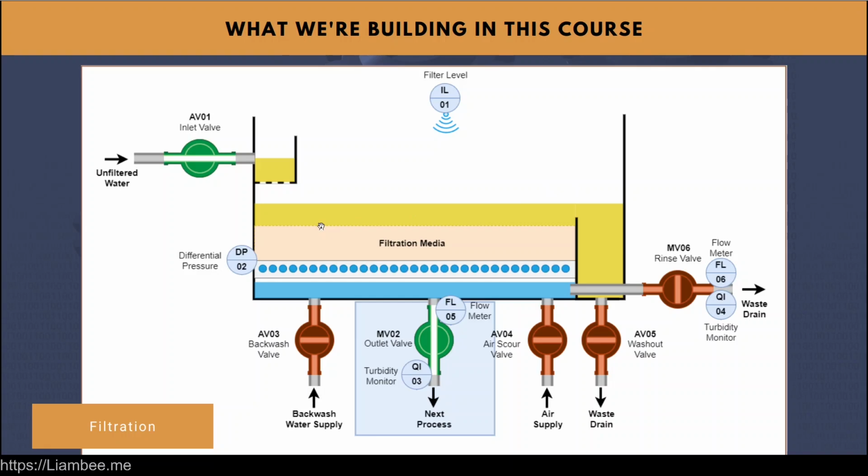So what we do is we reduce down into an interlock UDT. So we create the status, which we've already done in this asset here in the quarter turn valve asset data, that says whether it's failed to open, failed to close, or whether it's unhealthy. And we then write that to an interlock. So we'll have a look at that now.